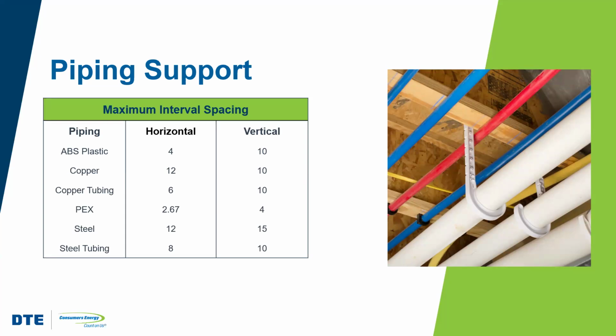We want to make sure that our piping system is adequately supported. We want to make sure that the supports are compatible materials with the pipe itself, and that we don't exceed the maximum interval spacing for those supports, so that we don't have any sagging or bending. We don't want the pipes to be moving excessively, because this could cause leaks or failures. These thermal stresses can also reduce the life of the piping, right? Or make the pipe require additional maintenance, and we don't want to do those things. So we want to make sure that they're supported properly with compatible materials, at proper interval spacing.